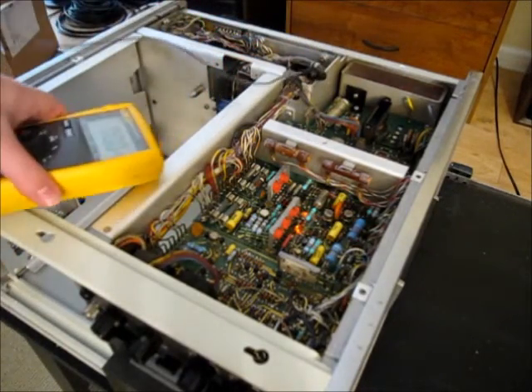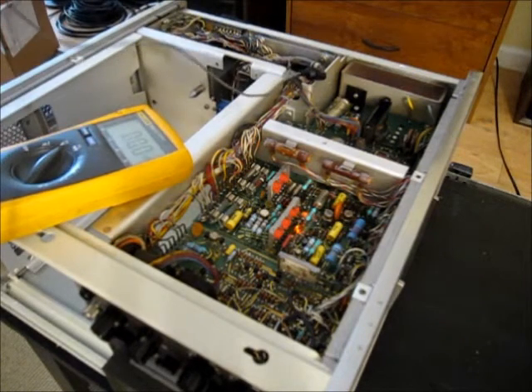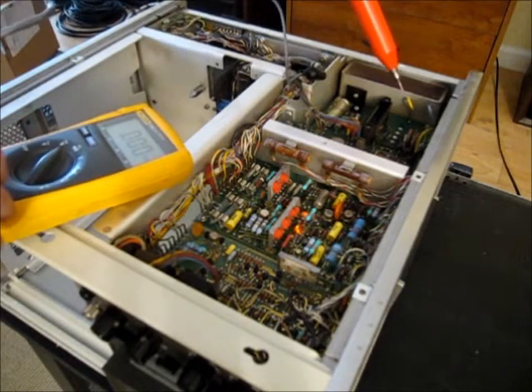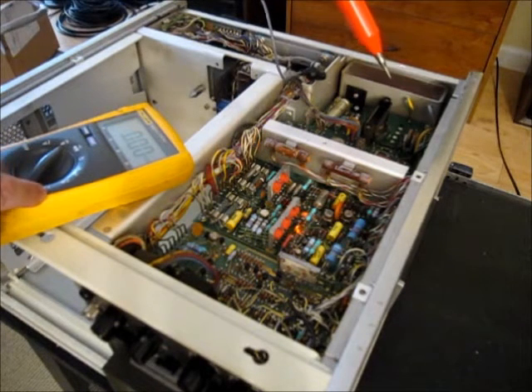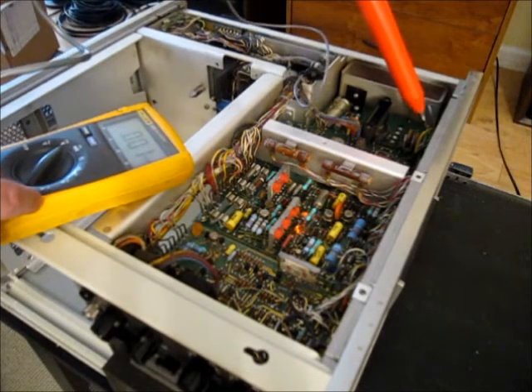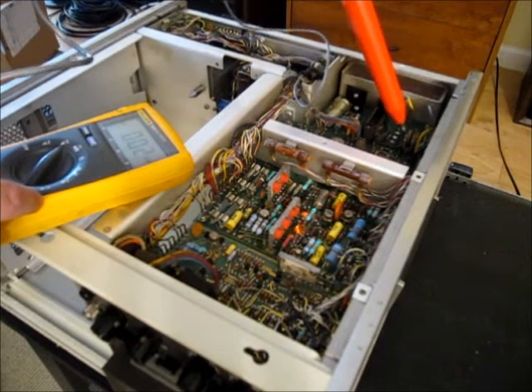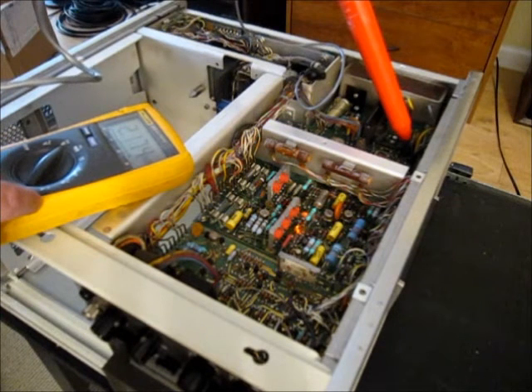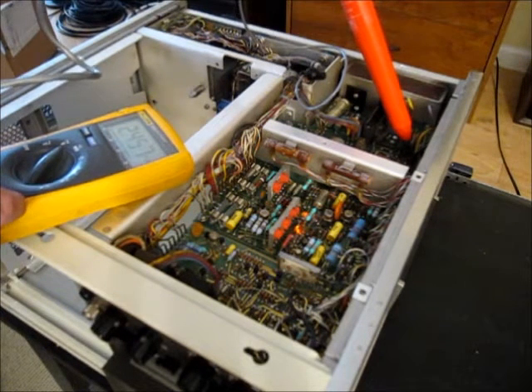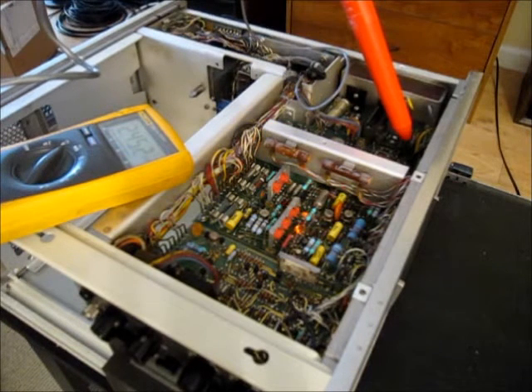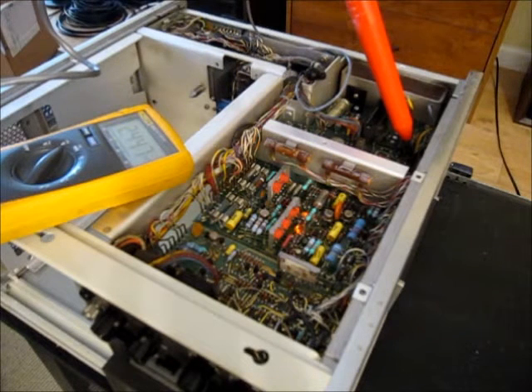And then the high voltage section that we want to measure, the high voltage rail, is negative 2,350 volts, and it can be measured off of this green wire right here. So you're going to touch it to the connection on the board right there. And I know for a fact that this probe measures a little bit low, about 2% low. So I sort of correct for that afterwards. But I am actually reading this to be a little bit high.